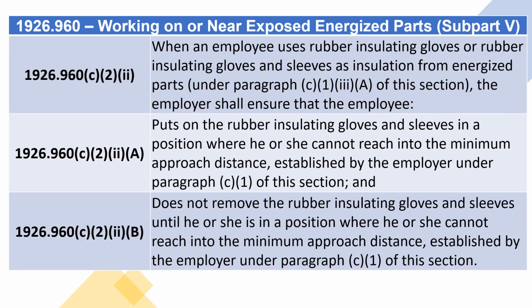1926.960(c)(2)(ii) When an employee uses rubber insulating gloves or rubber insulating gloves and sleeves as insulation from energized parts, under paragraph (c)(1)(iii)(A) of this section, the employer shall ensure that the employee 1926.960(c)(2)(ii)(A) through (c)(2)(ii)(B) puts on the rubber insulating gloves and sleeves in a position where he or she cannot reach into the minimum approach distance established by the employer under paragraph (c)(1) of this section, and does not remove the rubber insulating gloves and sleeves until he or she is in a position where he or she cannot reach into the minimum approach distance established by the employer under paragraph (c)(1) of this section.